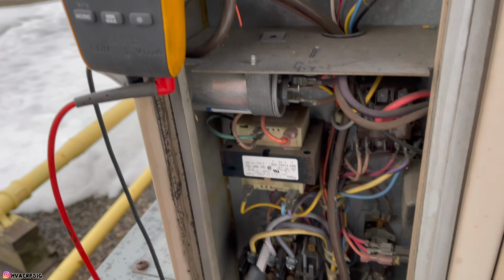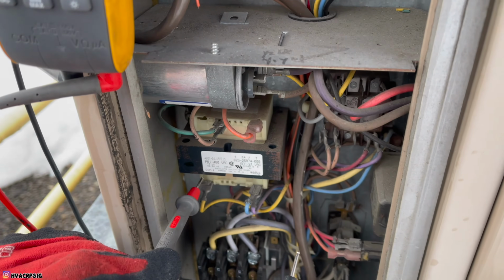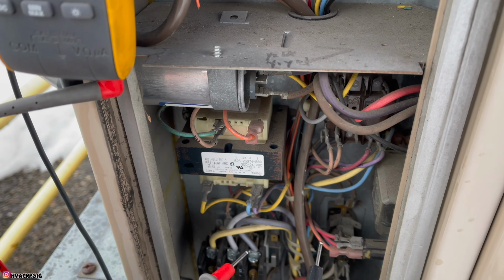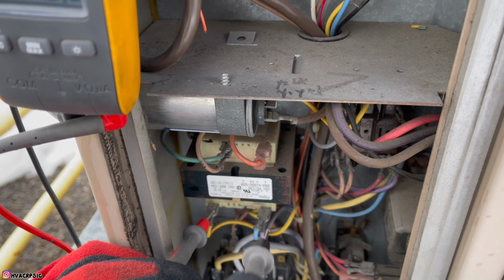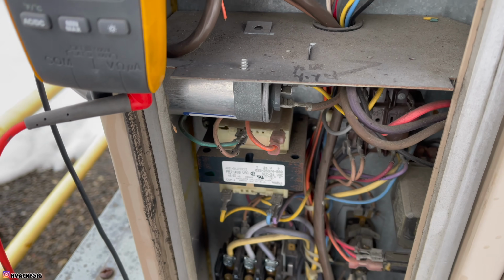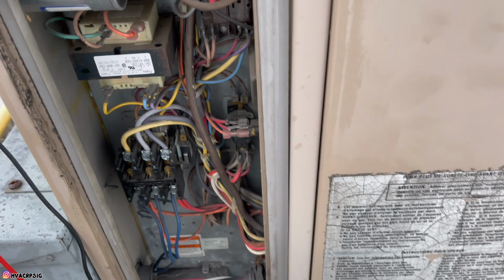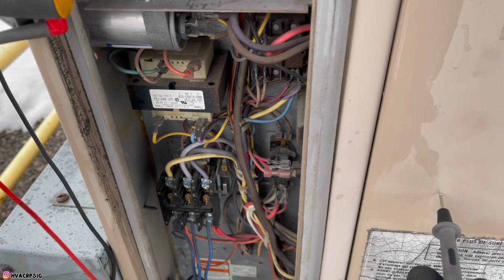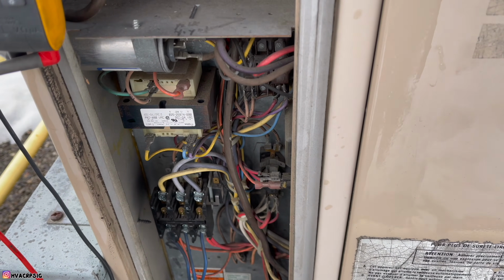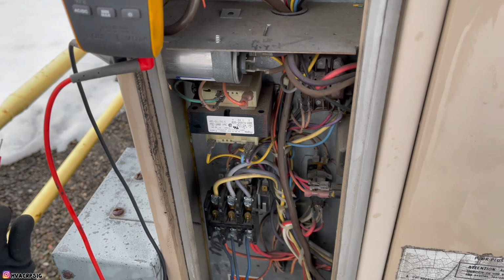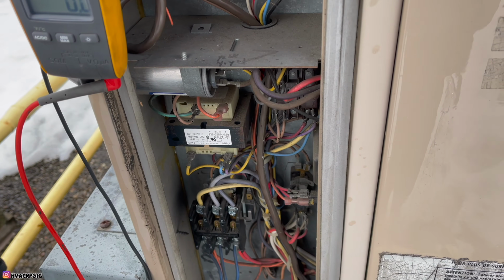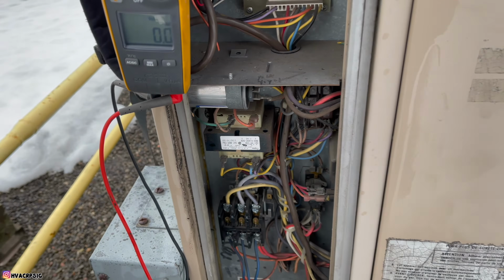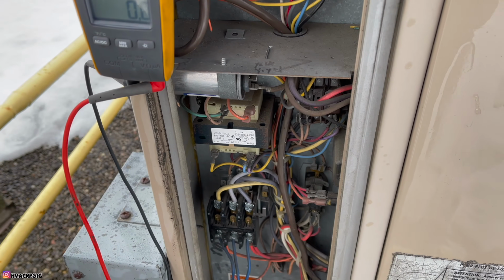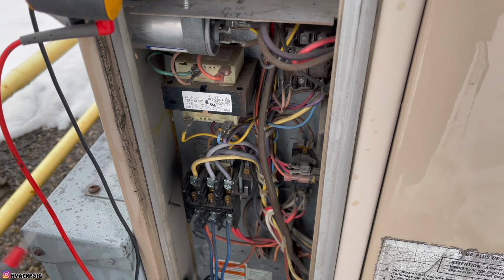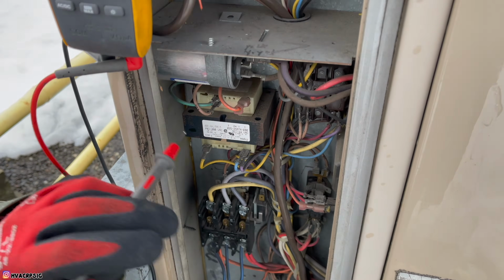Our phase is good. Now we're gonna check the transformer. Should have 480 or 460, somewhere between there. Tell them why. There's two transformers on this unit. There's one located under there. Basically, the indoor blower, the venter motor, and the condenser fan motor run off of 460. That's right. These units, when they ship up from the States, the older ones, they don't have 600 volt, but they do make the compressor 600 volts. That's right. I guess because there's enough compressors, they see that there's value to do it, but everything else they kept as 460, it's easy to manufacture.